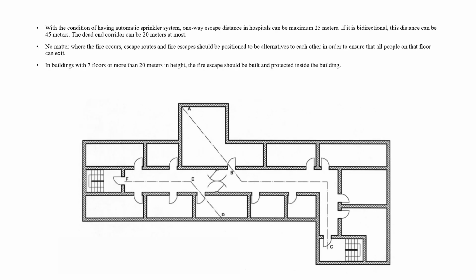With the condition of having an automatic sprinkler system, the one-way escape distance in hospitals can be a maximum of 25 meters. If it is bidirectional, this distance can be 45 meters. The dead end corridor can be 20 meters at most.